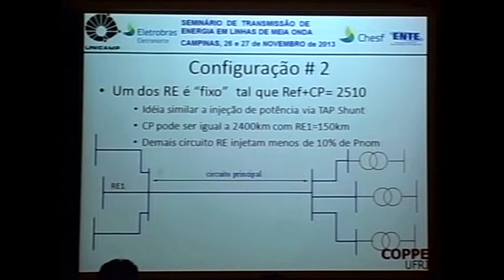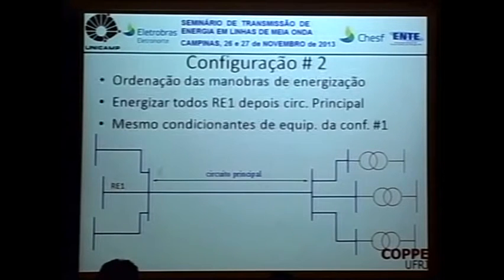Here, the idea is I fixated one and connected the other points. So in this study, we allowed that once you connect here, from this point on you do the energization, and the others are going to be connected afterwards. The order of maneuver is something that I cannot escape. I'm always going to have to prioritize them because, depending on them, the demands on the circuit breakers are going to be different. So I have the same conditions from configuration 1, but with the advantage that my main circuit could be a little bit shorter.